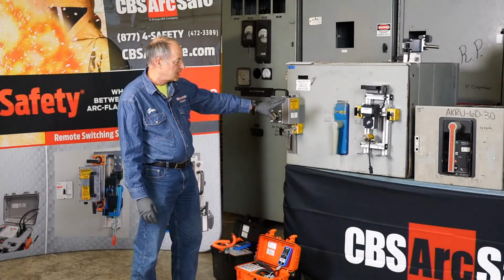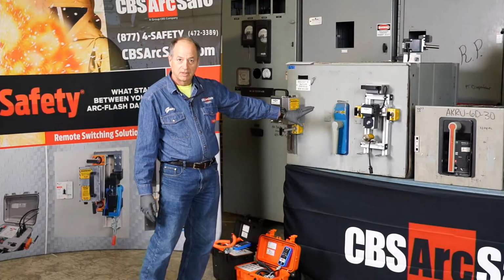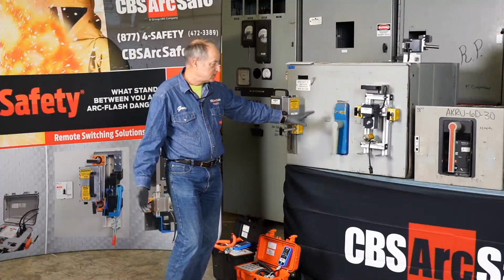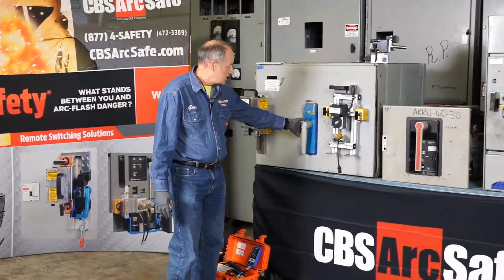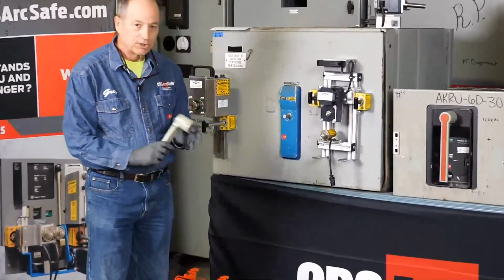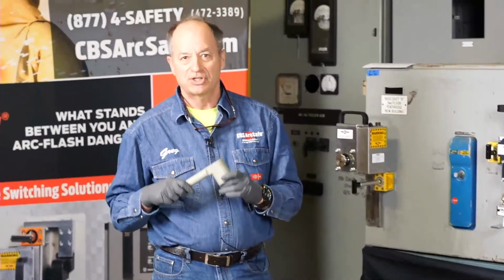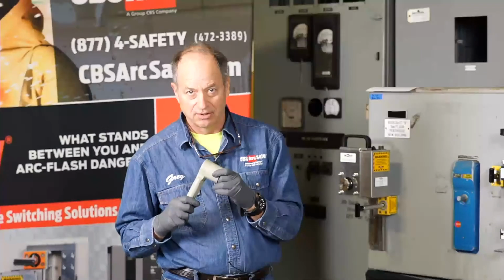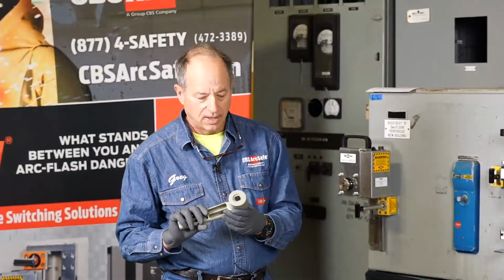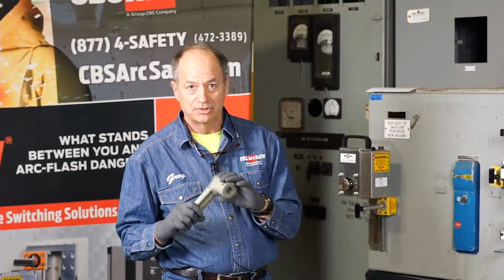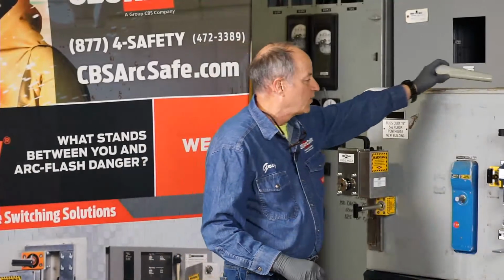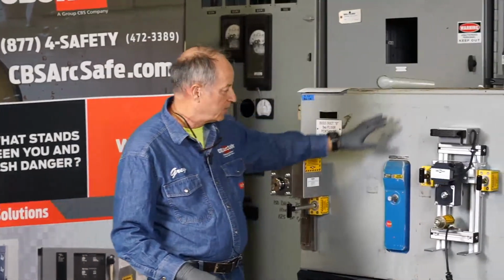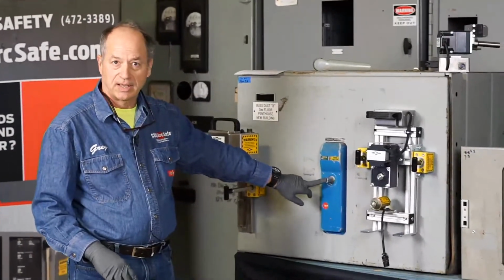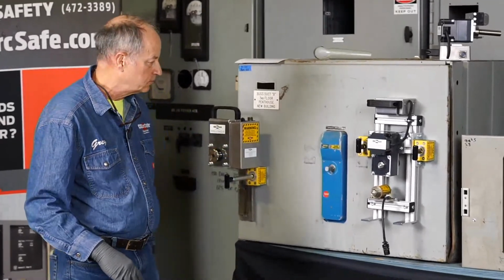This is the AKD5 switchgear, made from about 1960 to 1977. With a GE breaker, there are actually 2 set screws inside this handle that you have to take off in order to get the handle off. Once you back out both set screws, you can take the handle off, and then we can fit our remote switch actuator over the charging handle.